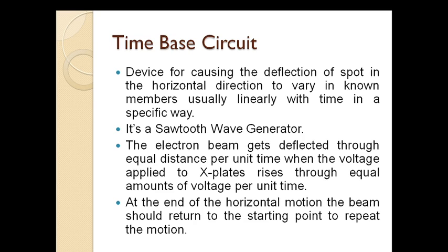This circuit is connected to the X plates, so that when the time base circuit is switched on, it automatically produces a sawtooth wave which is given to the X plates. The sawtooth wave generated by the time base circuit starts creating the horizontal deflection on the screen of CRO in such a way that it covers equal distance in equal intervals of time, and at the end of the horizontal deflection it brings the spot back to the starting point to trace the signal again.